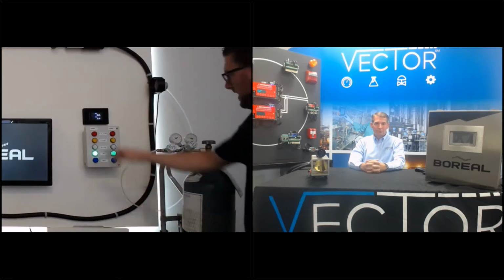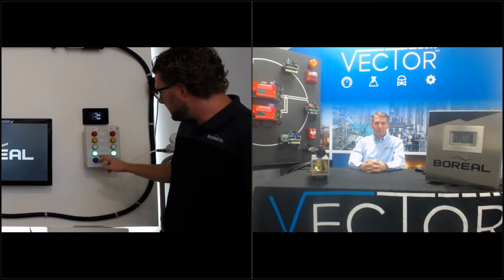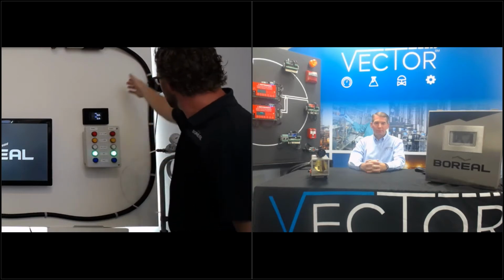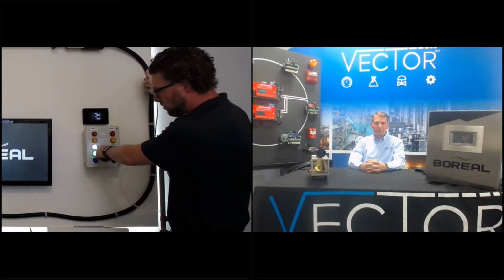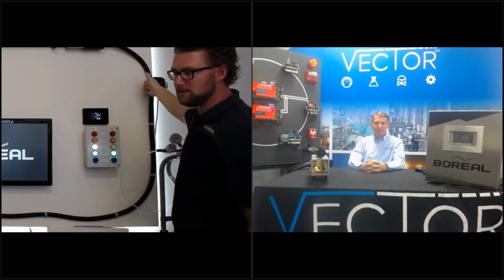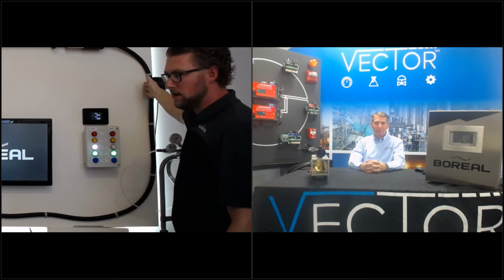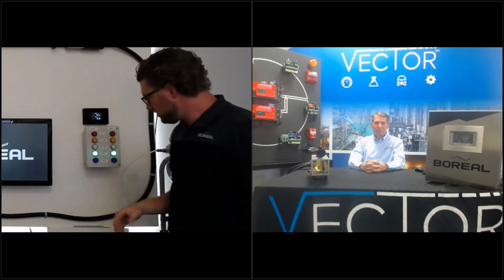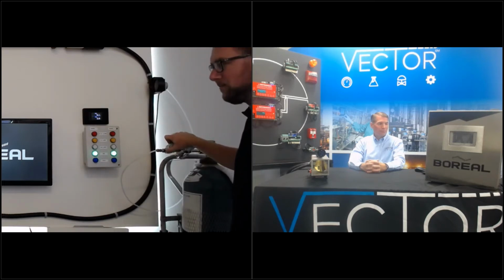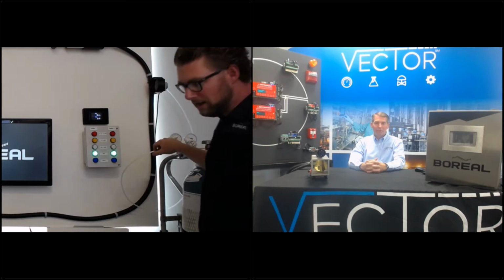As I zoom in here and get out of the way, what we have here are indicator lights that are tied to the relay module outputs of this particular analyzer. The green light that we're seeing here says the system is on, working, and functional. If I block the laser beam of this particular path, the relay will come on and activate, showing that we have a status condition of a beam block. A general fault condition and a beam block are treated differently under these sorts of examples.